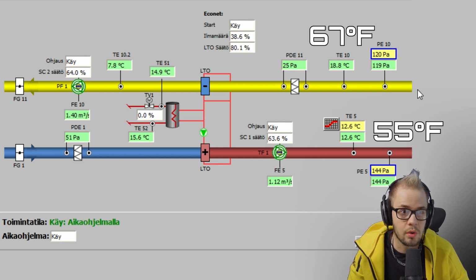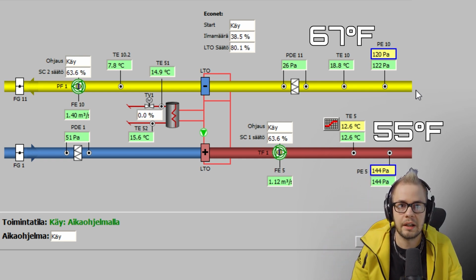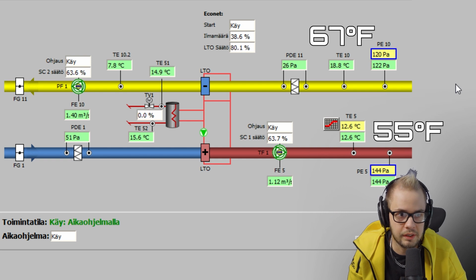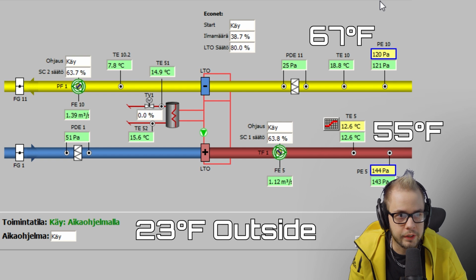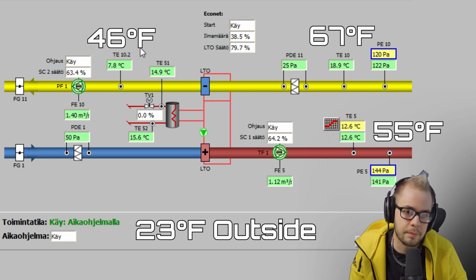It's not actually that low because there's some heat exchange happening in the building itself, but that is what the ventilation machine is getting. Then there's another filter, the heat exchanger circuit again, and then it gets exhausted. Here we can see we have an overabundance of heat currently. It's minus 5.1 degrees outside, and our heat recovery has been set to about 80%, so we are not running it at full steam. The exhaust air currently is 7.8 degrees.